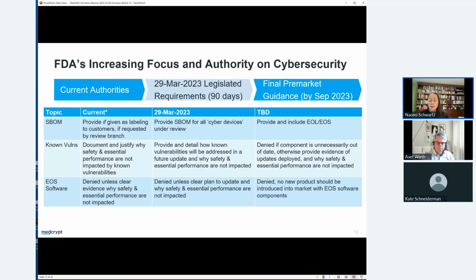So today, FDA is looking for things like a software bill of materials if it's provided as part of labeling to customers, or if it's requested by a review branch, for example. Known vulnerabilities should be documented. Manufacturers should be justifying why safety and essential performance are not affected by these known vulnerabilities. Typically, the known vulnerabilities are listed in the software bill of materials if it's asked for, but they should be included even if an SBOM was not asked for.